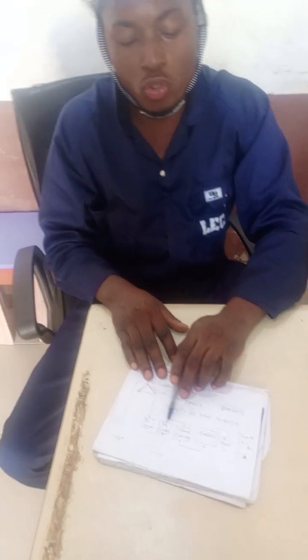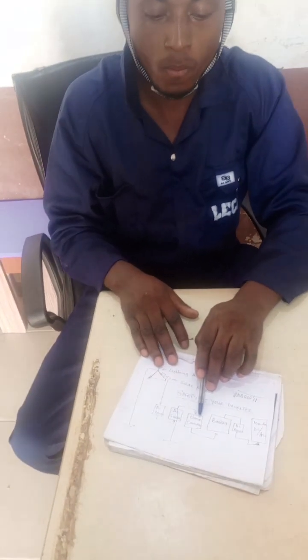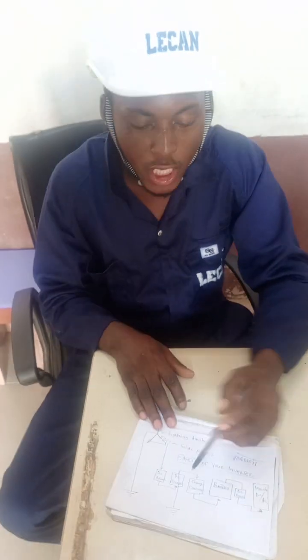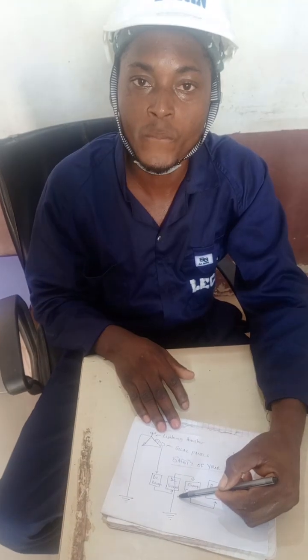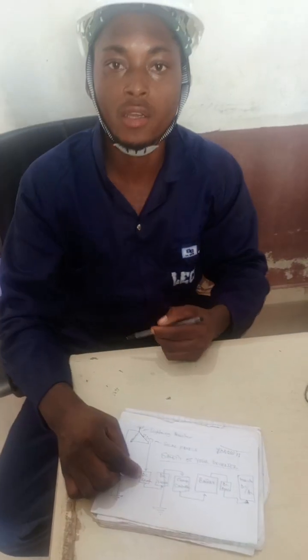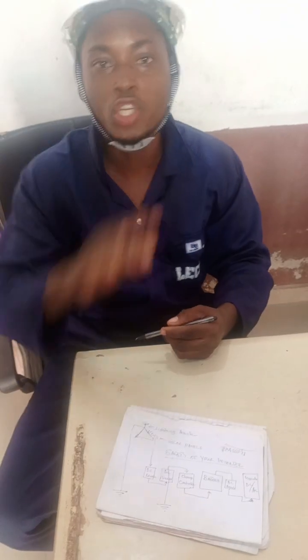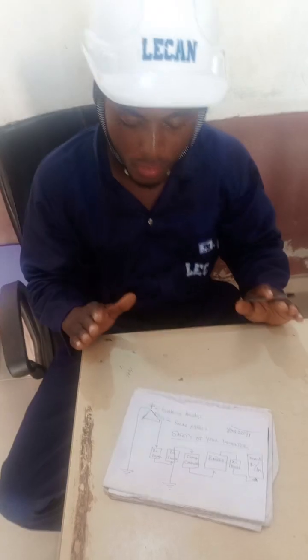So any excessive voltage that is coming will stop here. It will be unable to what? To go to your charge controller. And when that excessive voltage is being grounded, there will be excess currents. The excess currents can trip your breaker. So your breaker will trip off and keep your system very safe for you.